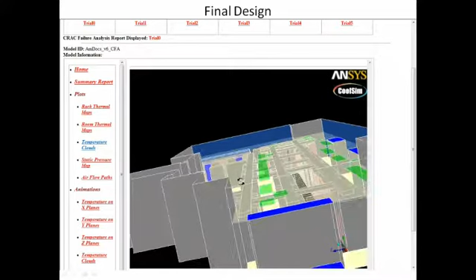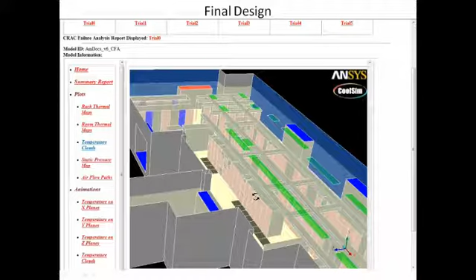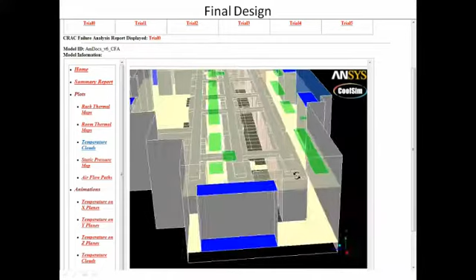Yeah, exactly. So looking at the iterations for how improvements will be made, first we created the pod. That's going to allow them to migrate some of the higher density loads from that legacy or older infrastructure into the pod, as well as consolidate other equipment from some of the other global sites. Once that's done and we get back to a relative new baseline, they can take steps to start improving the existing space that wasn't touched as part of this. One of those things was adding a little bit of cold aisle containment for the existing infrastructure on the shared cold aisle, shown in this simulation.